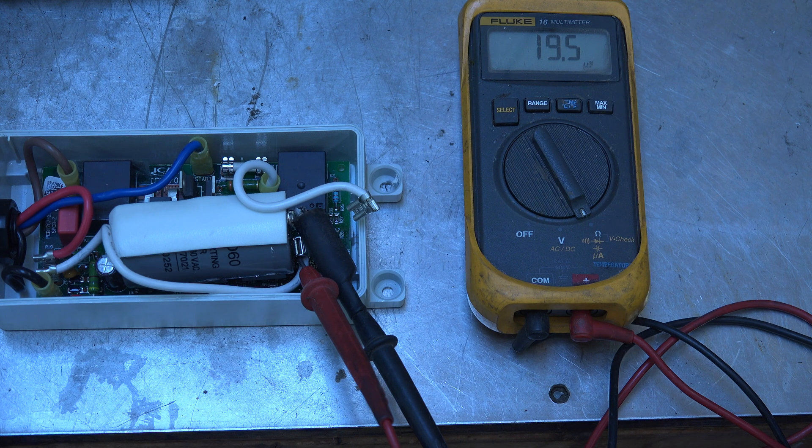I tested the other components and didn't find any problems. On the new install it was reasonably easy to install and it operated as expected. However, a failure after about a year is a little out of hand. My full load amps on the compressor was 16.7 and it's rated for 16 — but I don't think that made any difference.